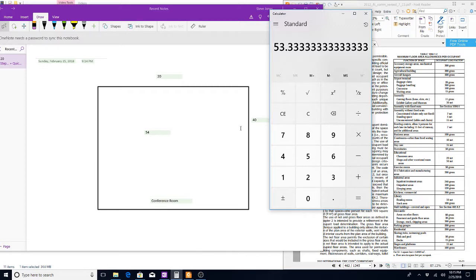The occupant load is 54. In a conference room, any time you have more than 49 people, a few different requirements kick in. When you have more than 49 occupants in a conference room, you are required to have two exits. So this room would have to have two exits.